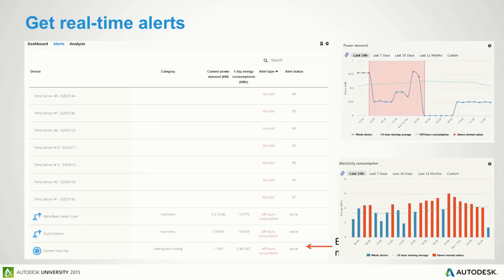You can drill down into the actual device and see what's happening down to a 5-minute interval. If it's flagged as off-hours consumption, you can go in and see why that device was on during off hours, and whether other issues were flagged before that event happened - meaning, has that equipment been consuming power more than its normal rated power?